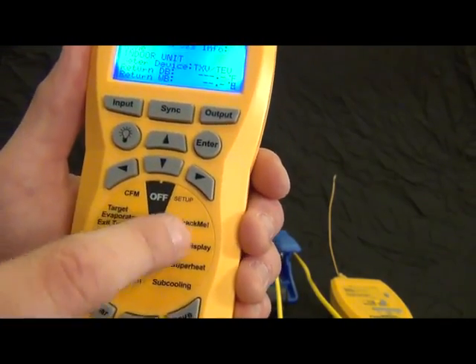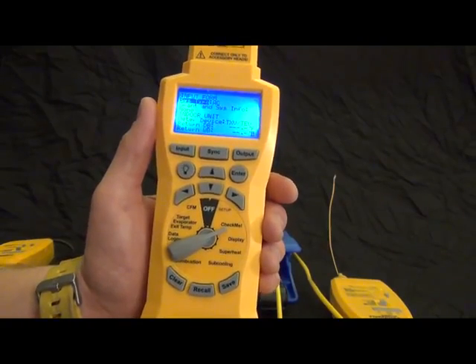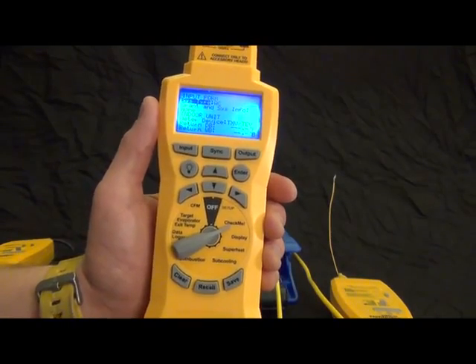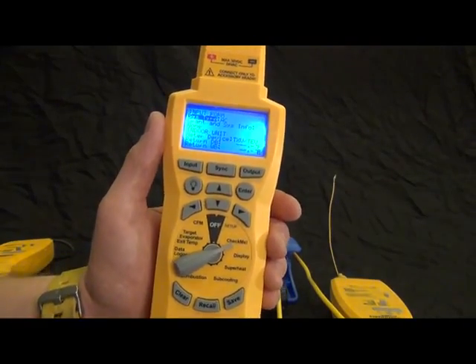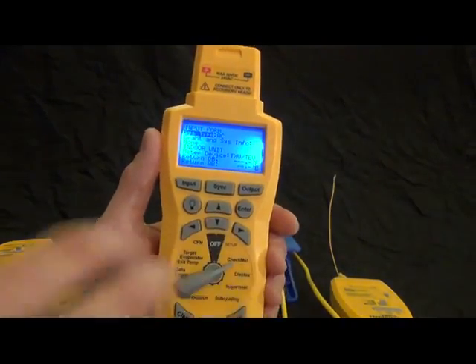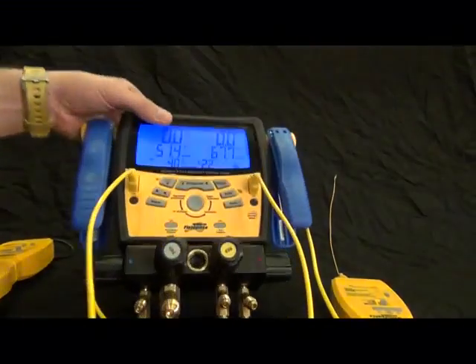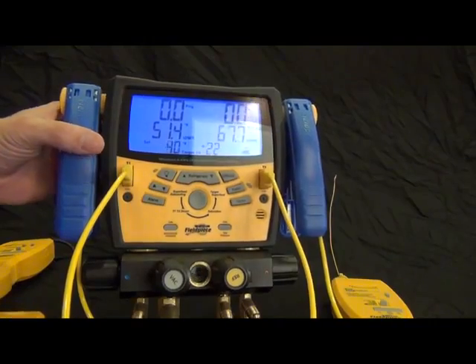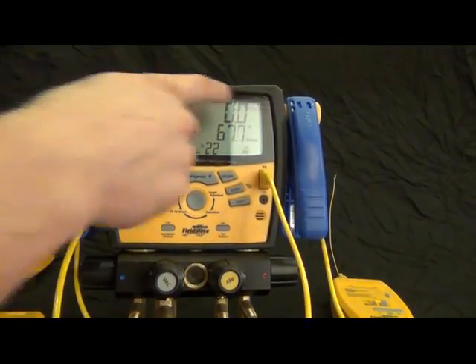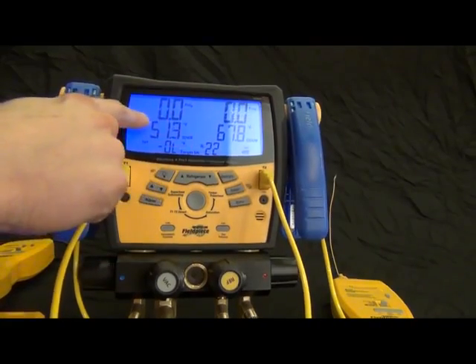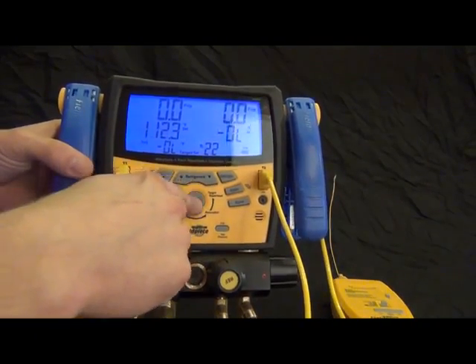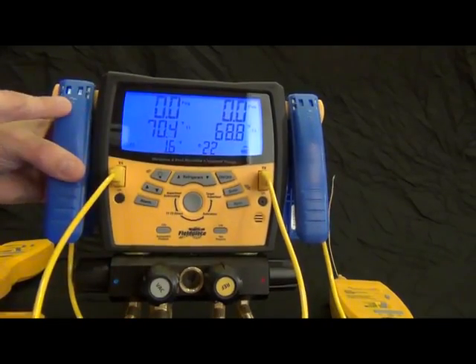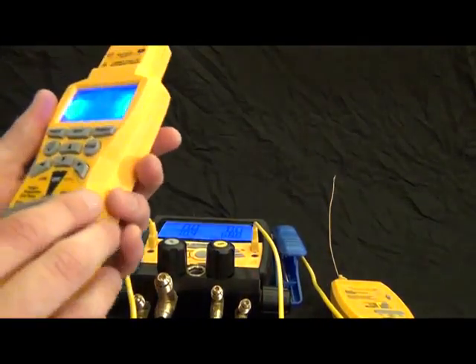CheckMe basically combines delta T, superheat and subcooling into one test. It completely looks at the entire system and all the measurements involved. It takes about 10 pieces of data and calculates and diagnoses a system based on those 10 pieces of data. So what the S-Man 4 is responsible for is for six of those pieces of data. It's going to transfer liquid and suction line pressure, suction line temperature, indoor wet bulb, outdoor dry bulb and also suction line temperature and liquid line temperature. So it's going to transfer all six of those to the HG3.